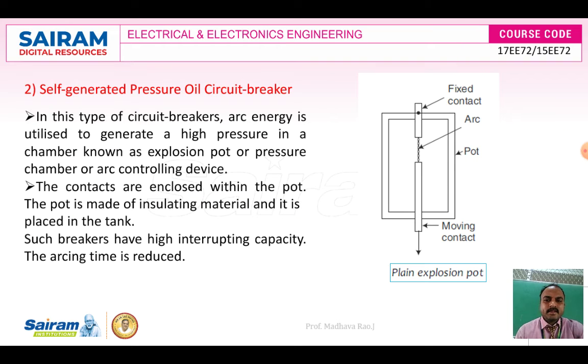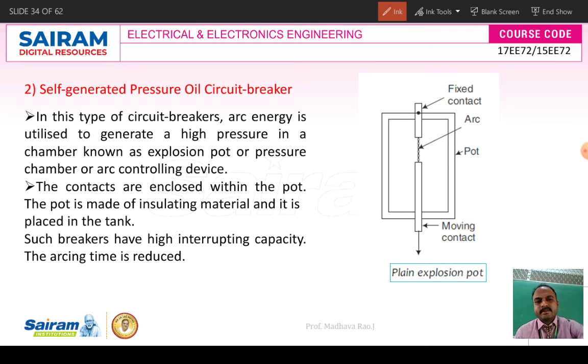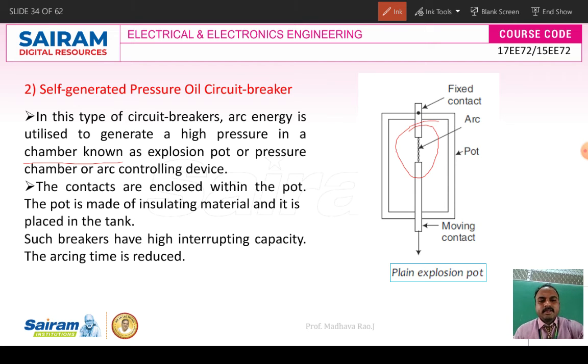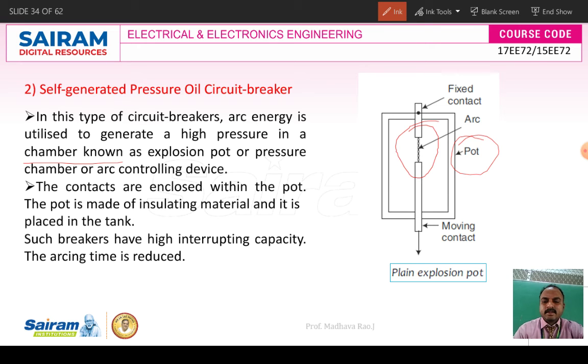The self-generated pressure oil circuit breaker does not have a first break and second break — it has only one break where the arc forms. These contacts are placed in a chamber known as an explosion pot. Inside the pot there is oil, and the pot is made of insulating material and placed in a tank. Such breakers have high interrupting capacity and reduced arc time. Whenever a fault occurs, the arc is produced and the two contacts separate.